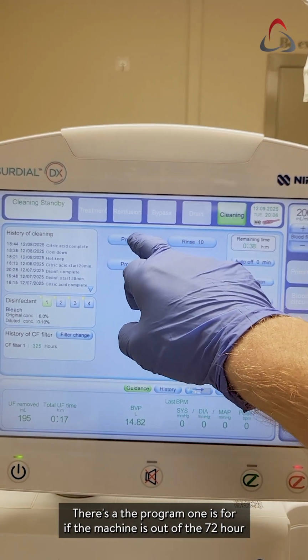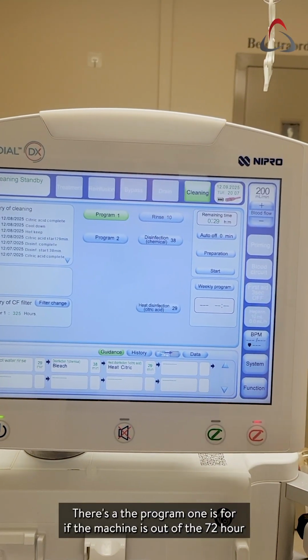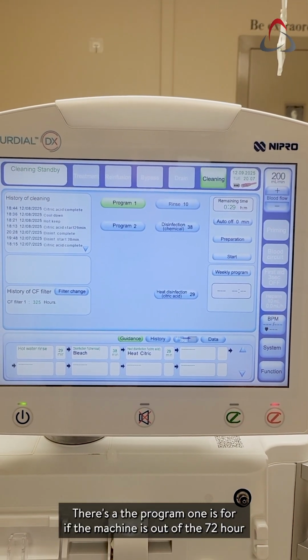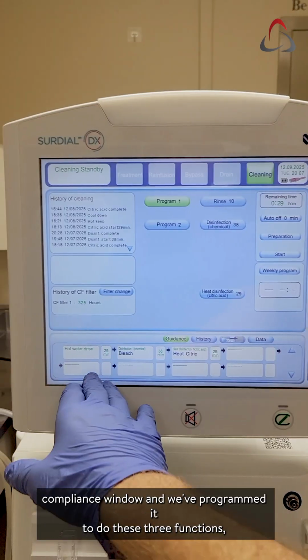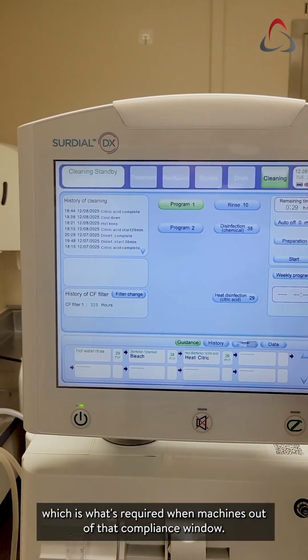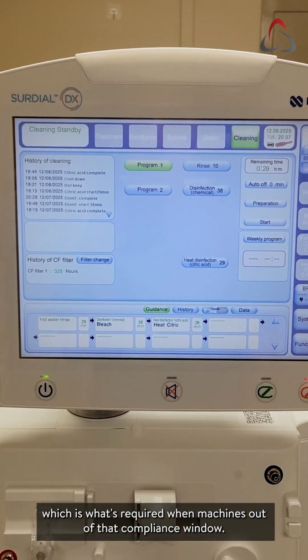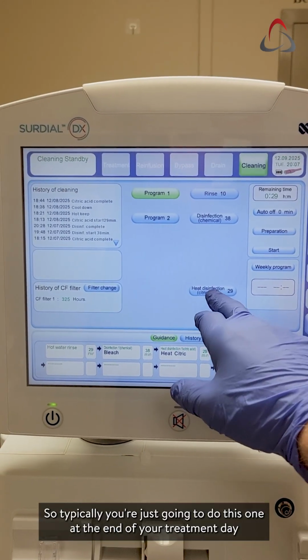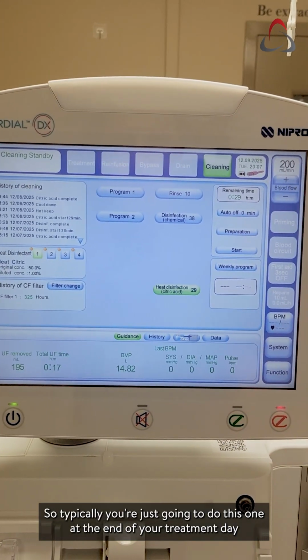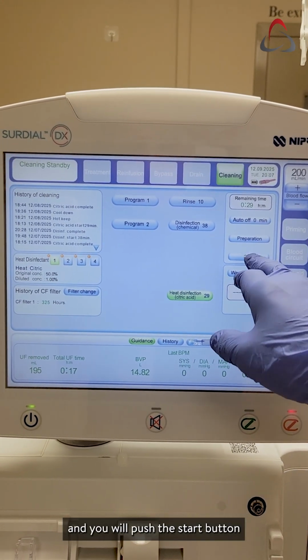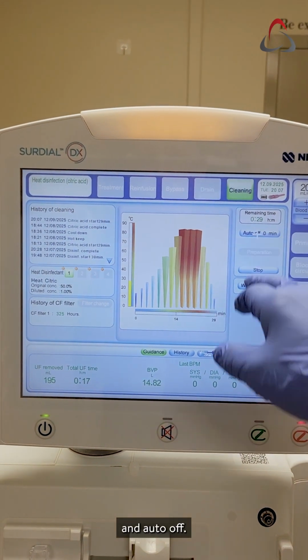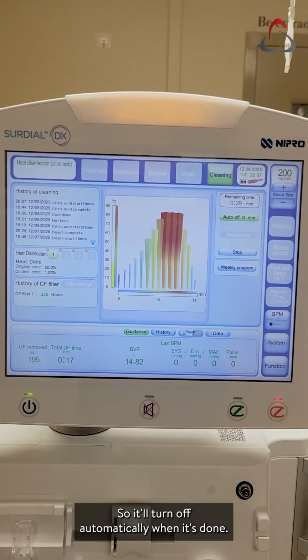Program 1 is for if the machine is out of the 72-hour compliance window, and we've programmed it to do these 3 functions, which is what's required when the machine's out of that compliance window. Typically you're just going to do this one at the end of your treatment day, and you push the start button and auto off, so it turns off automatically when it's done.